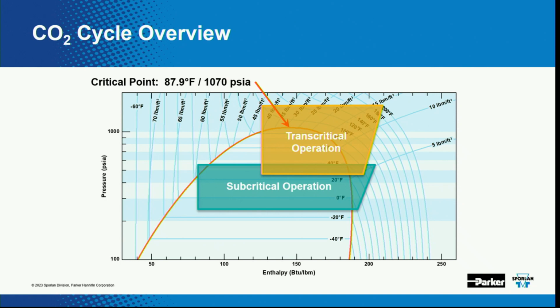I will say that it's interesting. If you're north of this vapor dome, you're in what's called a supercritical fluid. Supercritical. Super is above. So superheat is the temperature above saturation. It's that delta above. Supercritical would be the temperature above the critical point.